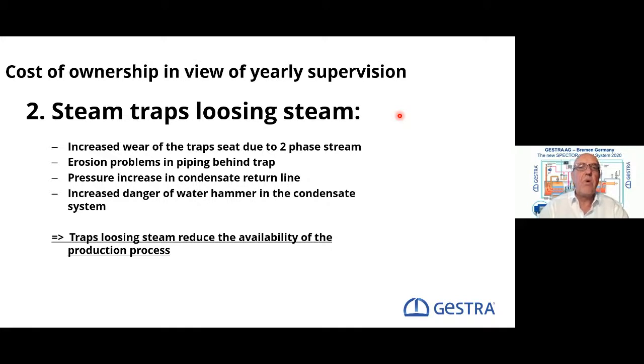that an orifice which cannot close anymore has these erosion problems, and then also erosion problems in the piping behind the steam trap. The pressure can increase in the condensate return line, and this influences all other steam traps in the plant, so that they maybe have not the capacity anymore, because the pressure drop is lost because of the pressure increase in the condensate system, and that also normally leads to an increased danger of water hammer in the condensate system. And so it could be said at the end that traps losing steam reduce the availability of our production process.